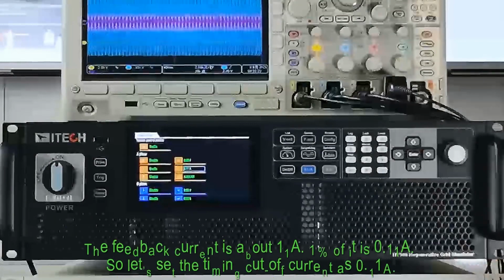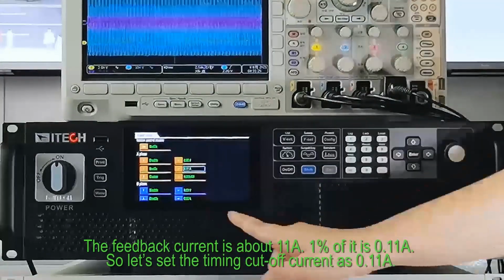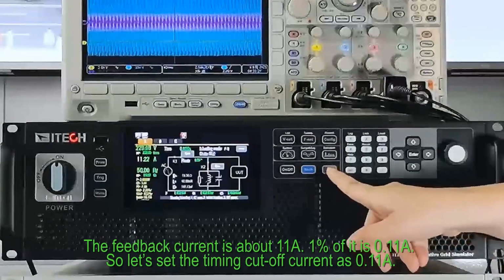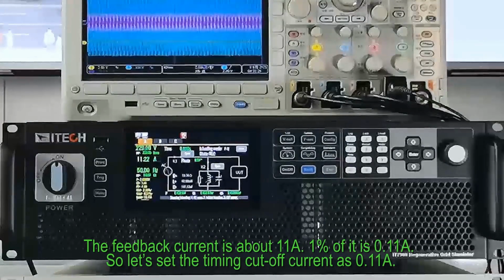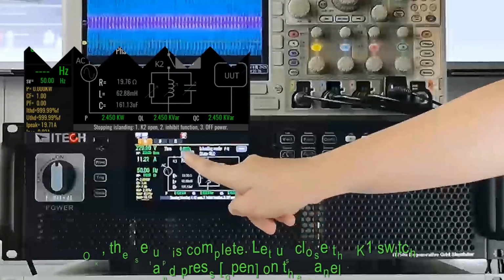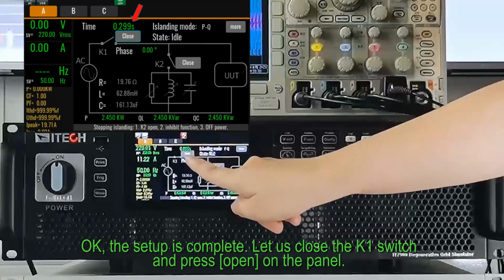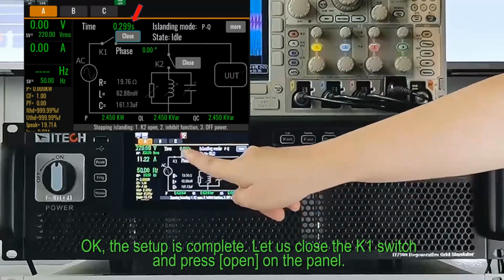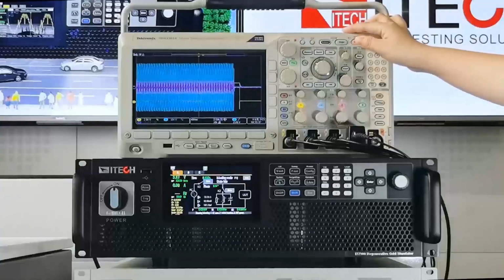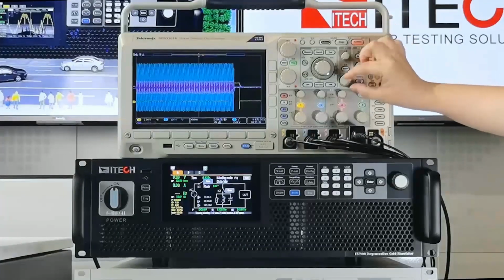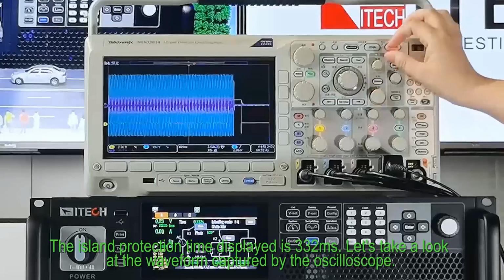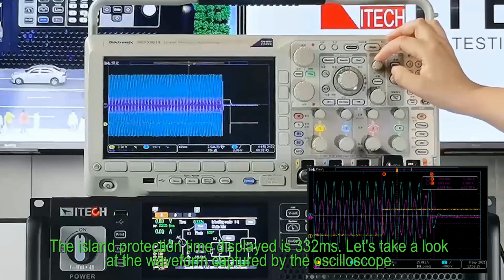Here we set the current as the cutoff condition. The feedback current is about 11A. 1% of it is 0.11A. So let's set the timing cutoff current as 0.11A. Okay, the setup is complete. Let us close the K1 switch and press Open on the panel. The islanding protection time displayed is 332 ms.